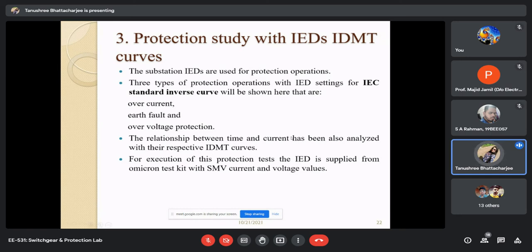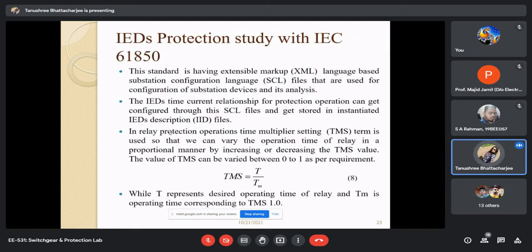So that type of curve we have obtained in these three types of protection. Over voltage actually doesn't follow any IDMT; that will be a fixed point of operation. So over current, earth fault and over voltage, three types of protection we have studied. There also we are using the TMS value.